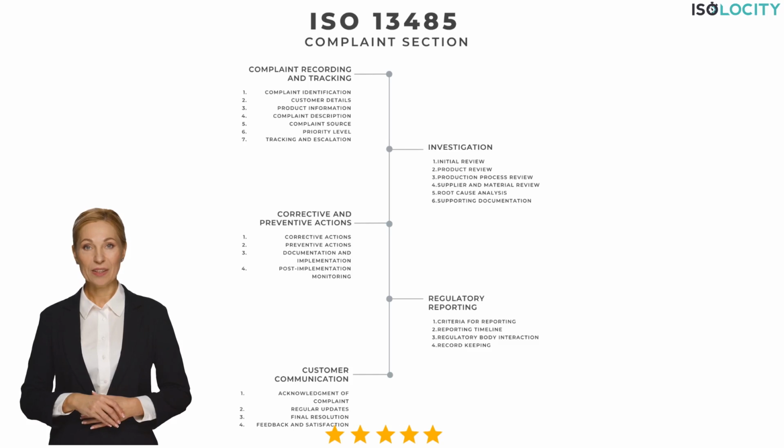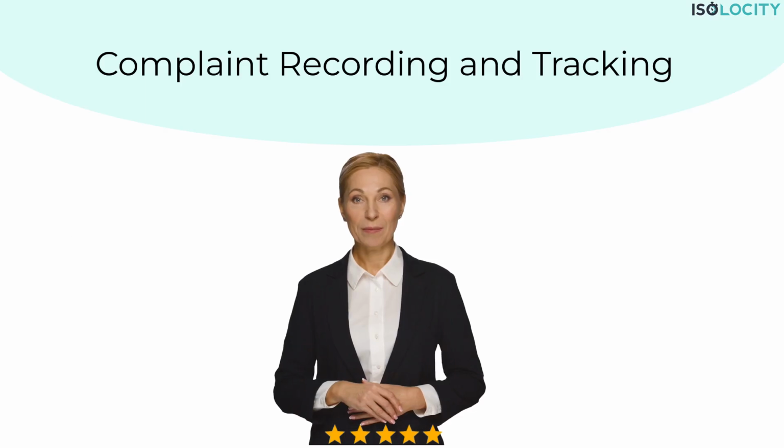The complaint section is all about identifying, analyzing, and fixing any product-related issues that come up after your device hits the market. The whole point is to keep customers safe, stay compliant, and continue improving your product. Here's what the ISO 13485 complaint section covers. Complaint recording and tracking. You need a system to log and track complaints. This includes details like the complaint's origin, description, and any product defects.